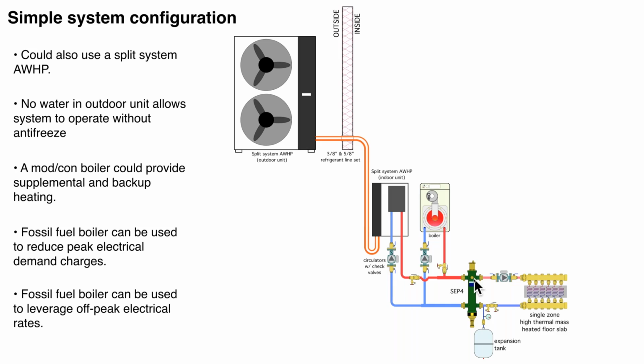The other nice thing about the boiler is in utility areas that have demand charges on commercial meters, which is common, you could avoid a high electrical demand that you would have, for example, with an electric boiler by using a fossil fuel boiler. So it can be a peak shaving tool, a demand reduction tool, or supplemental heat input if it's very cold out and the heating capacity of the heat pump is not high enough to meet the building load. And finally, depending on the size of that boiler, we may have the ability to completely heat the building if the heat pump was down for service. So if we had a failure of the heat pump for whatever reason, we've got a full backup.